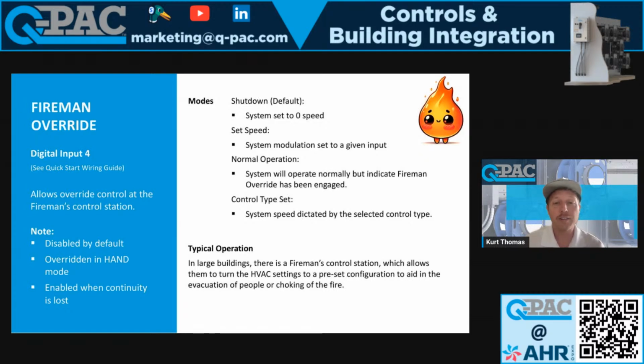And the fireman can switch a switch and toggle our system to go into Fireman Override, and we'll do whatever was preset. So if you want us to go to 0 speed, then we'll shut down the fans and we'll throw an alarm and say, hey, we're in Fireman Override. We can go to a set speed. So if you say, hey, I don't want you to run 100%, but I want you to run 60% or 80%, in the event that Fireman Override is enabled, then we can do that. We can just continue to operate normally.